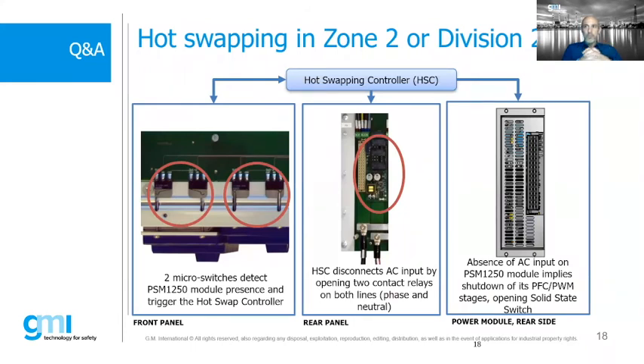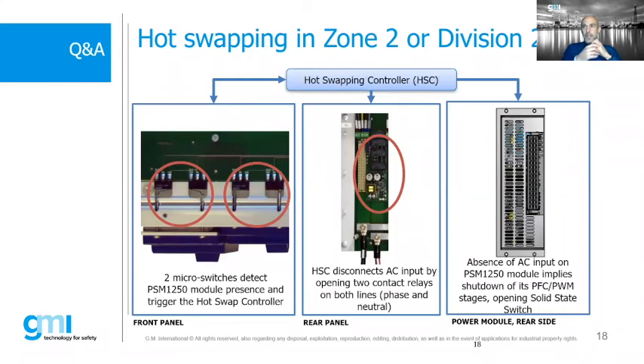So the single modules can be removed from the rack, here on the blue one. You can remove the units. And in case you're using a redundant configuration, with two power supplies in a redundant system, the other module, or the other modules, since you can have more than one in the redundant, will take over the power supply for the system without shutting it down. So you can keep the system working while you are maintaining or replacing the power supply unit. There are some switches inside that grant or allow the hot swapping. Yes, this is a mechanical system that allows us to discharge the internal electrolytic capacitors to avoid sparks in the dangerous area that can cause an explosion.